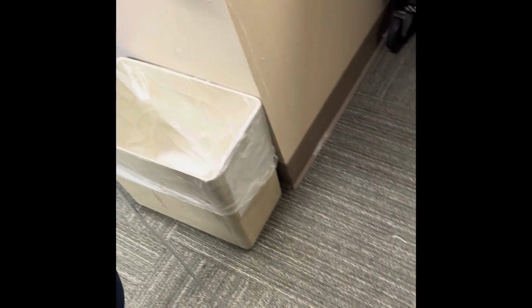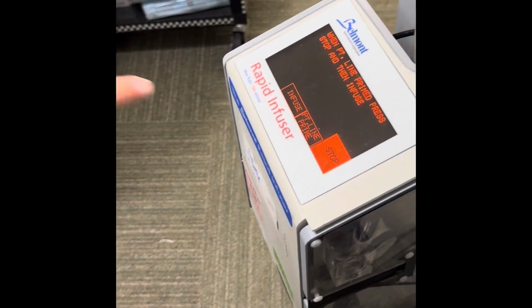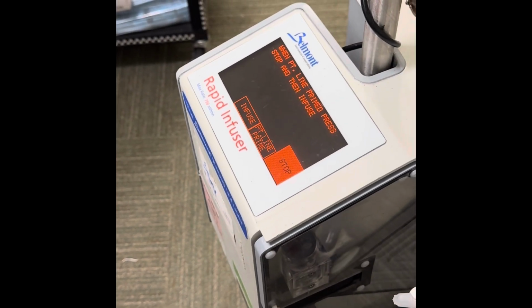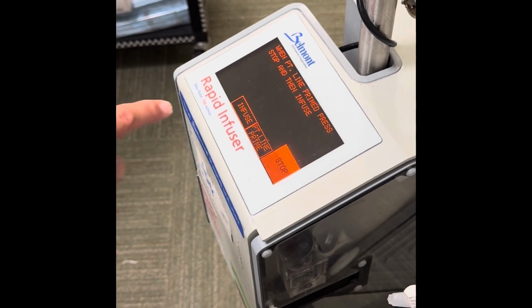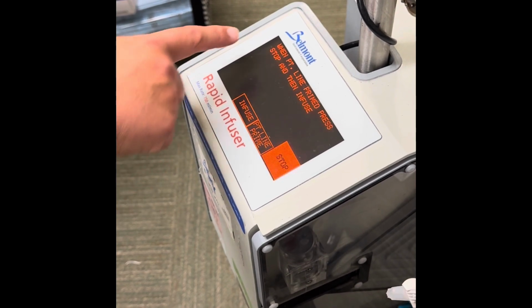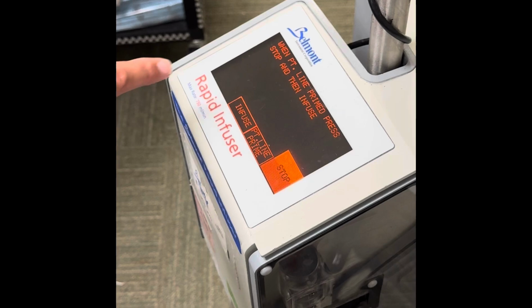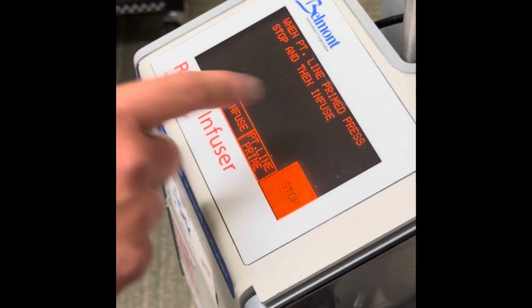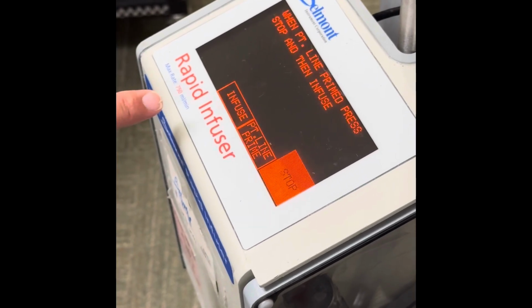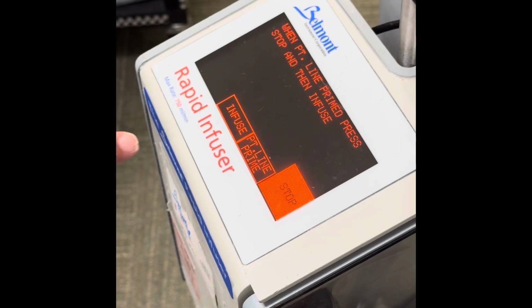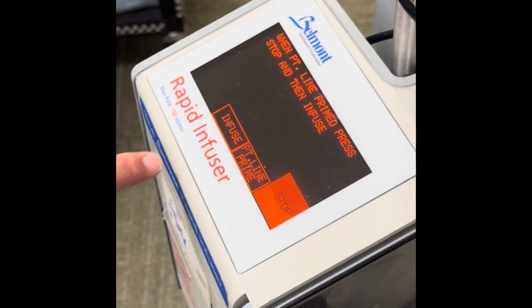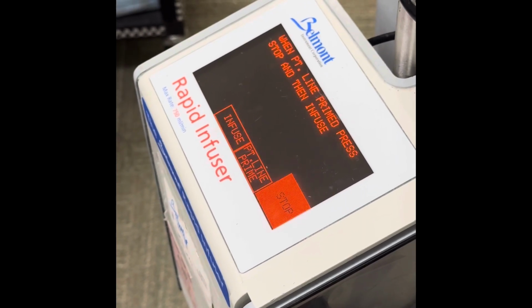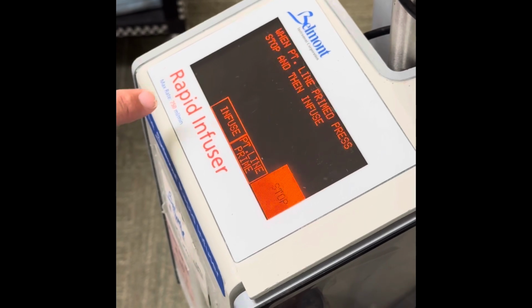Once I have primed that line, I'm going to press stop, and it's going to give me the option to infuse or prime some more. I'm going to tap infuse. I want to point out that the machine is very good at communicating with us and telling us what is wrong, because there could be a variety of different things that need to be evaluated. It could be air in the tubing. It could be there is a high pressure alarm because something is not infusing as fast as we would like.